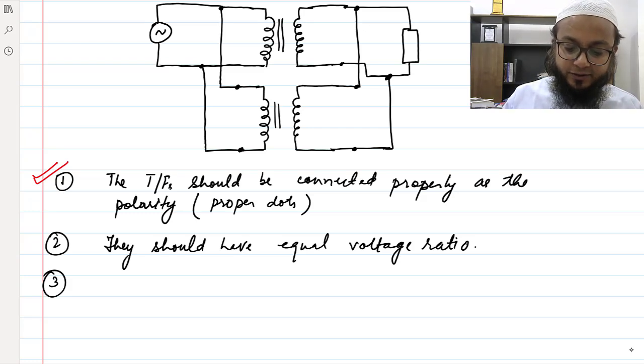Let's say 100 volt is the supply. So 100 volt on one transformer, 100 volt on another transformer, the primary of it. And secondary, let's say turn ratio is equal, so 200 volt here and 200 volt here. So then obviously you can short these two ends, right? And we'll see how, if this voltage ratio is not the same, then how it will cause the circulating current.